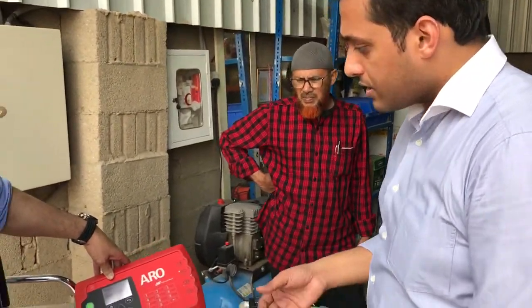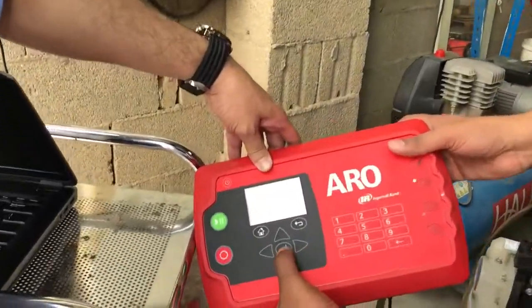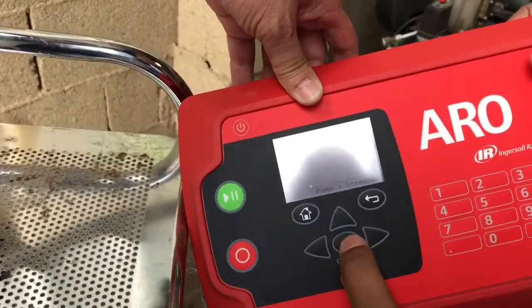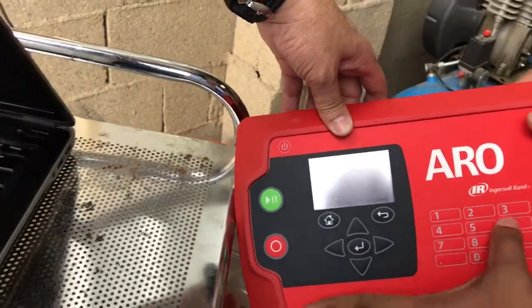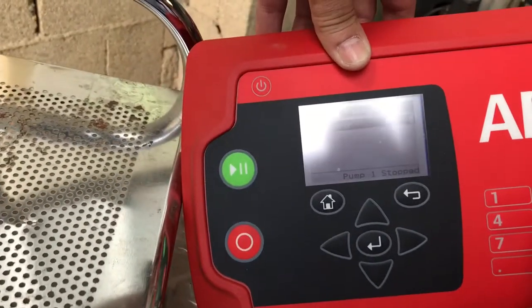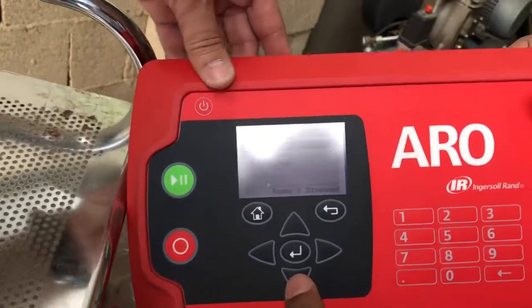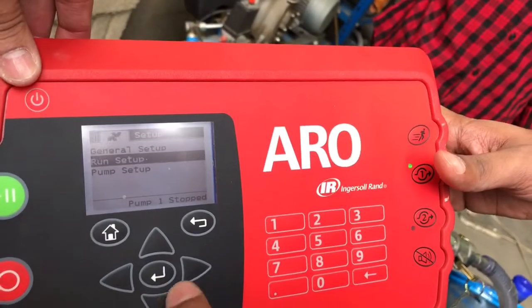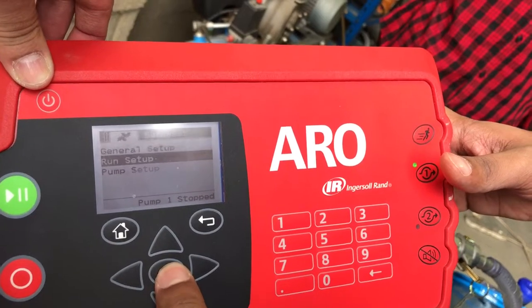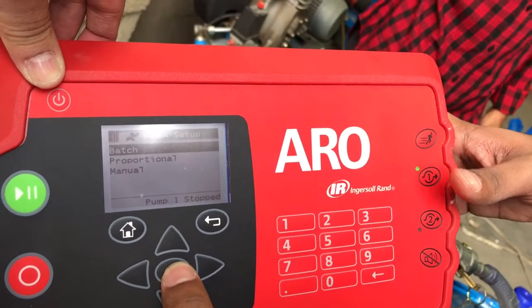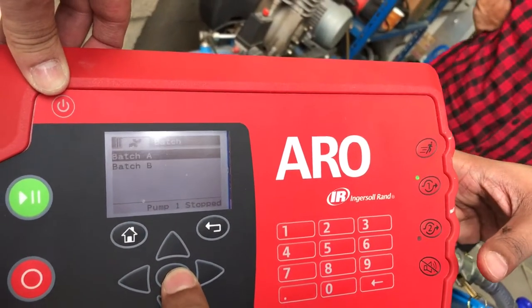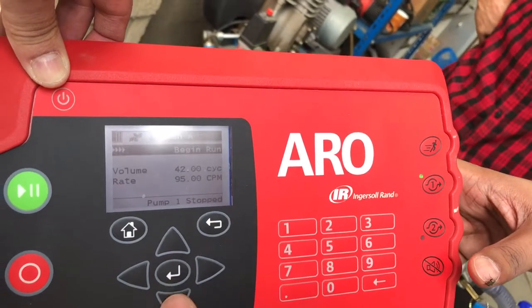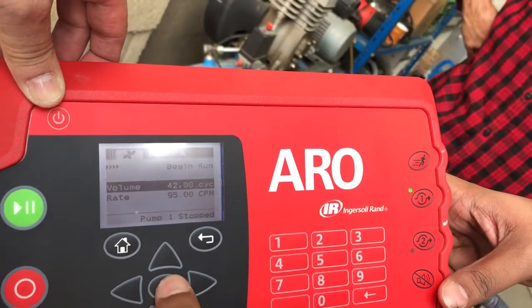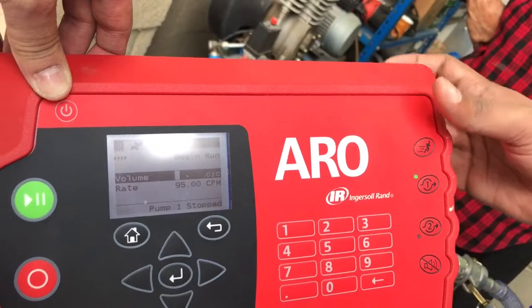So for calibration, that's why we are running the setup. Let's go to the setup. There's a password. The password is 27632, and enter the password. You have entered the setup mode. In the setup mode, go to the run setup. In the run setup, there is a batch mode. So go to the batch mode, batch A, select it, and you need 315 cycles.